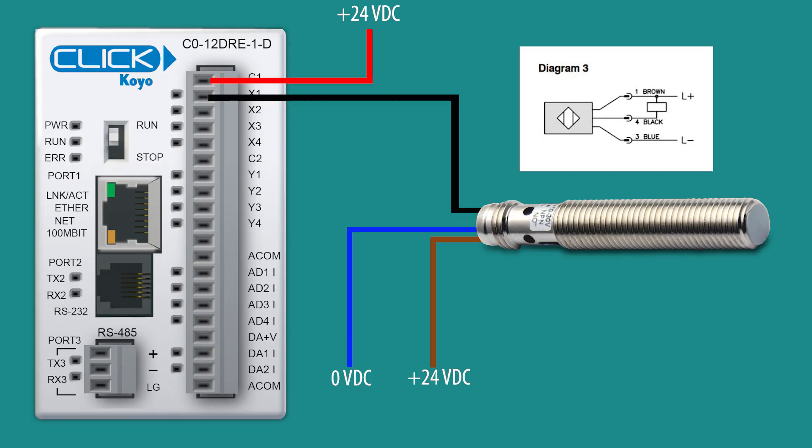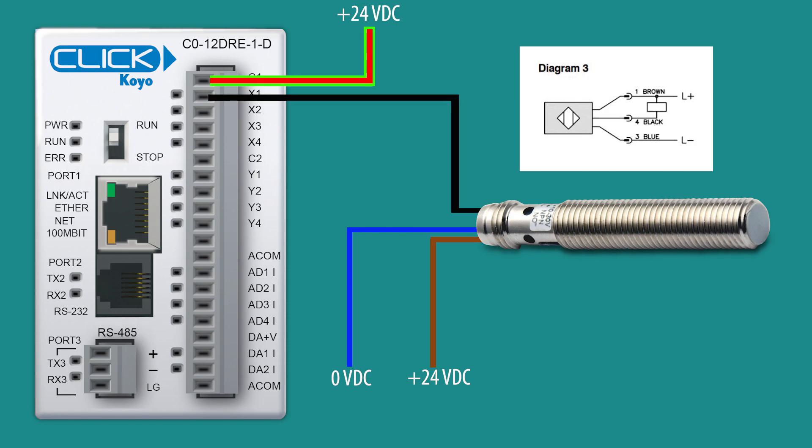I have an NPN inductive prox that meets the voltage requirements of the CLICK PLC. I will wire the output of the sensor into X1, and since this is an NPN prox, I will place positive 24 volts DC to the C1 common.